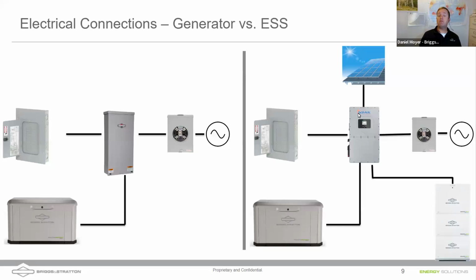Now, if we look at the right-hand side, what's taken the place of our transfer switch is the solar. Remember, the solar essentially has what's called a MID, or microgrid interconnect device, built into the Sol-Ark itself, so now the Sol-Ark is functioning as the transfer switch. In the same sense, we have grid coming through the meter socket, through a disconnect, flowing through the Sol-Ark—the pass-through, if you will—into our load center. If the grid goes down, the Sol-Ark detects that and disconnects us from grid, but it's not necessarily going to start the generator right away. It looks at the state of charge of the battery, how much energy is left, and only when needed will it start up the generator, when the energy reserves in the battery start to drop. So it's a much more dynamic system.